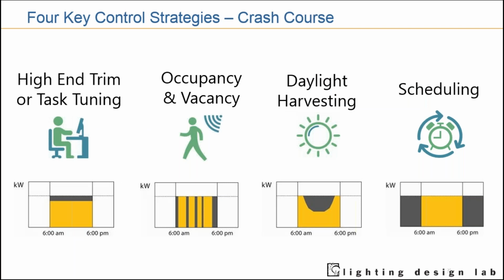Wanted to review a couple of these key control strategies and how they impact savings themselves. Again, from our 2019 NLC Best Practices Guide series, we're leveraging a couple of images, and we do have information on specific control strategies. As a quick review, high-end trim, also known as task tuning, is the ability to put a ceiling on the maximum output of a fixture or group of fixtures, automatically reducing wattage. The real reason it exists is because for good reasons, designers or specifiers will be conservative in speccing the lumen output of fixtures, not knowing if the walls are going to be all black or if there's going to be fixtures that are decommissioned. So to right size that illumination to ensure you have the proper foot candles for your task surface, you use that high-end trim to not glare your tenants and not use more light than needed in a space.